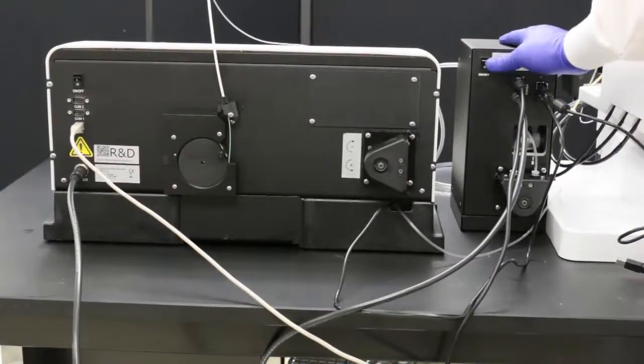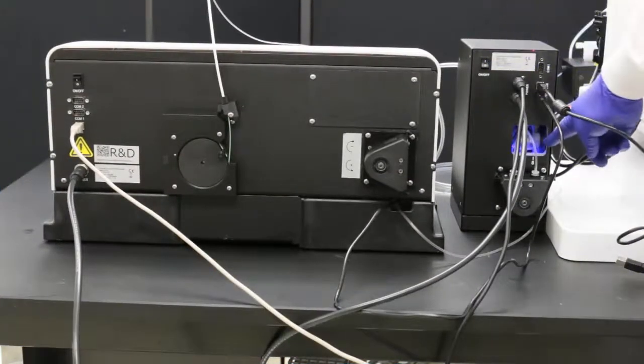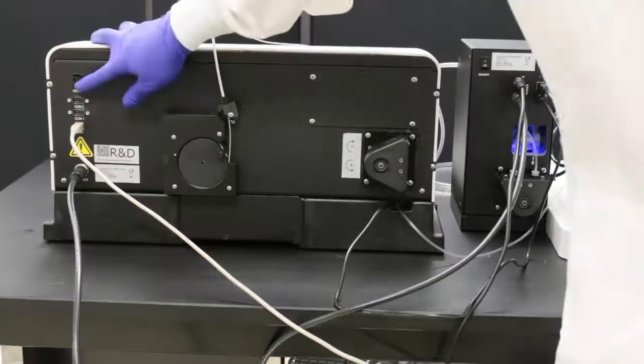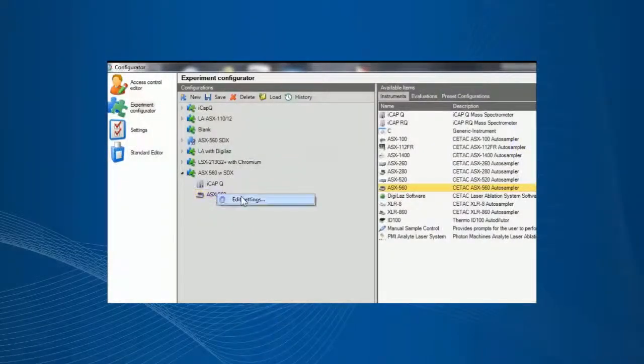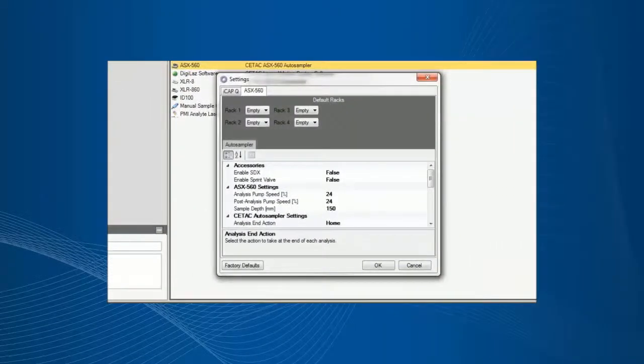Turn the SDX and the Auto Sampler on. When you turn on the SDX for the first time, the PC will assign a COM port number for the USB connection. The SDX is operated through a plug-in for your instrument control software. See the separate video on setting up Qtegra to operate the SDX.